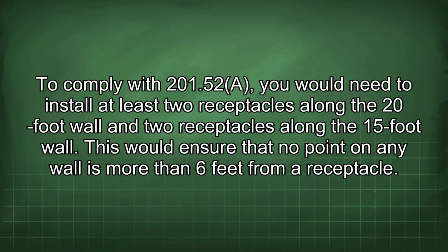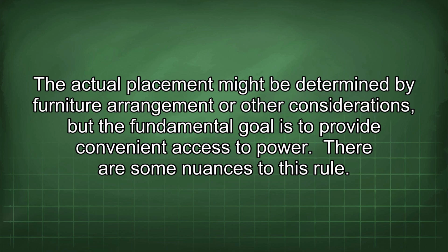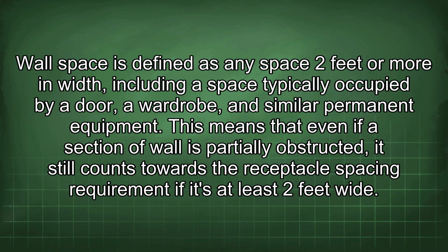This would ensure that no point on any wall is more than 6 feet from a receptacle. The actual placement might be determined by furniture arrangement or other considerations, but the fundamental goal is to provide convenient access to power. There are some nuances to this rule. Wall space is defined as any space 2 feet or more in width, including a space typically occupied by a door, a wardrobe, and similar permanent equipment. This means that even if a section of wall is partially obstructed, it still counts towards the receptacle spacing requirement if it's at least 2 feet wide.